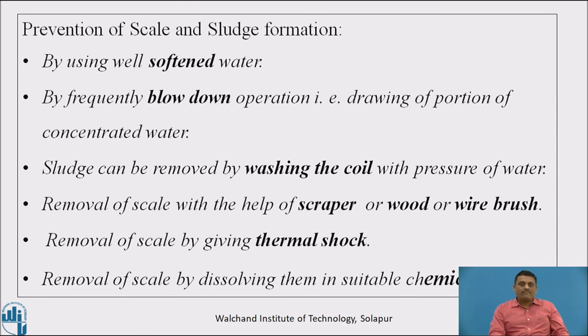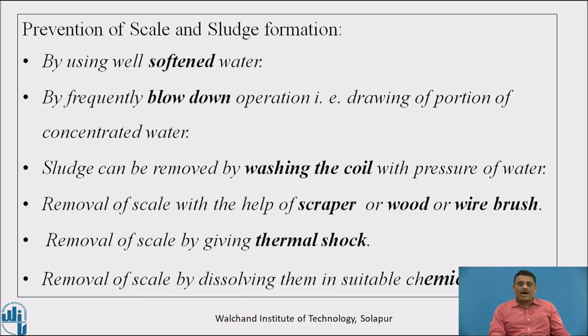Now, how to avoid scale and sludge formation? The first method is by using well-softened water — if softened water is used, there is no possibility of sludge and scale formation. Second, by frequent blow-down operation, drawing off portions of concentrated water. Sludge can be removed by washing the coil with pressurized water. Scale can be removed with a scrapper, wood or wire brush, by giving thermal shock, or by dissolving the scale in a suitable chemical.